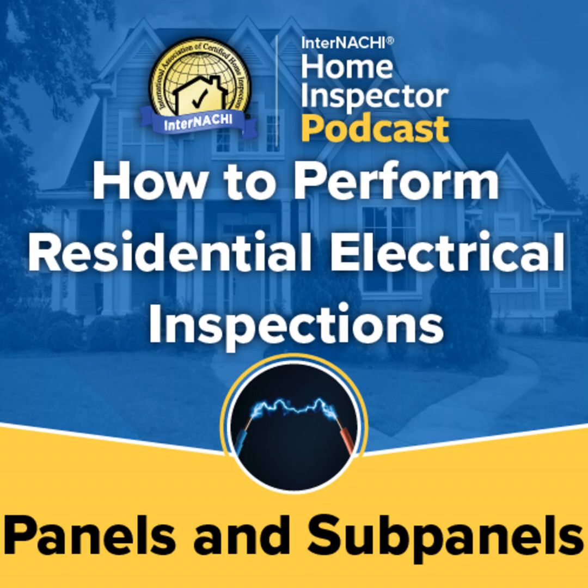Questions when inspecting distribution panels. When inspecting the distribution panel board or subpanel, an inspector may ask themselves: 1. How is the service grounded back to the service panel? 2. Are the neutrals and grounds separated? 3. Is the neutral bus isolated from the panel enclosure? 4. Is the panel cabinet connected or bonded to the grounding bus? And 5. Does each neutral conductor terminate at a separate lug on its bus?